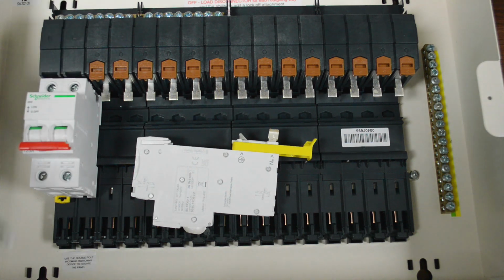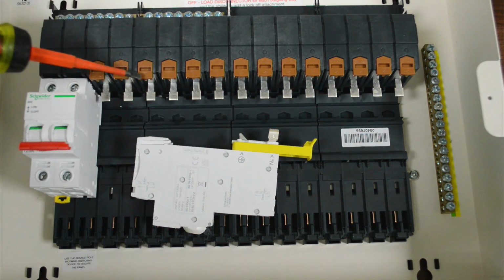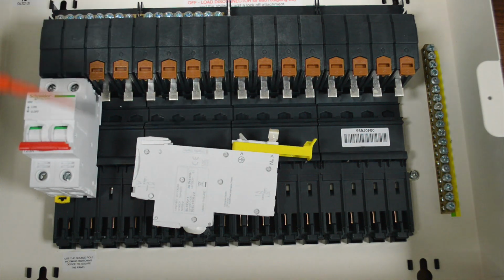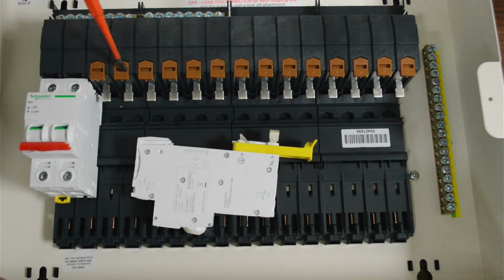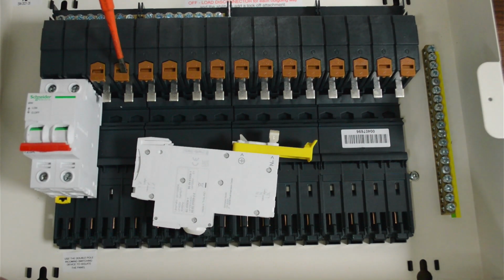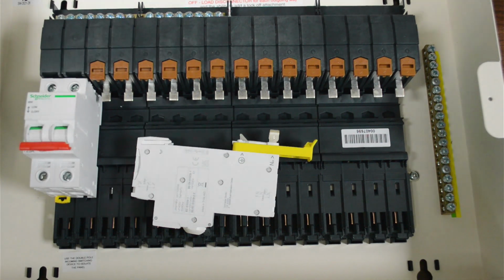You can disconnect and open up that main incoming switch. You can even go to the trouble of locking it off, but there's always the possibility of a mistake. If that was to happen, at least if these are exposed and these tabs are in, you know that they're not going to cause you an issue. And equally, if you try and actually push them out where there's no MCB locked in, they won't move. So it actually needs that MCB or RCBO to be in place.